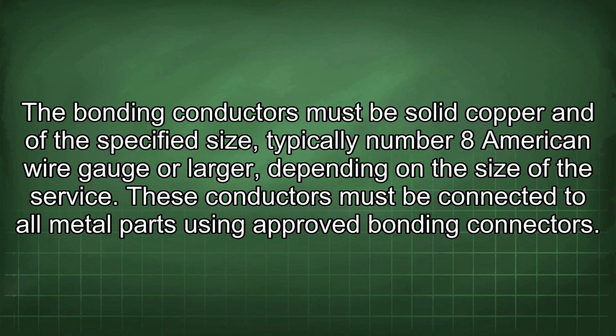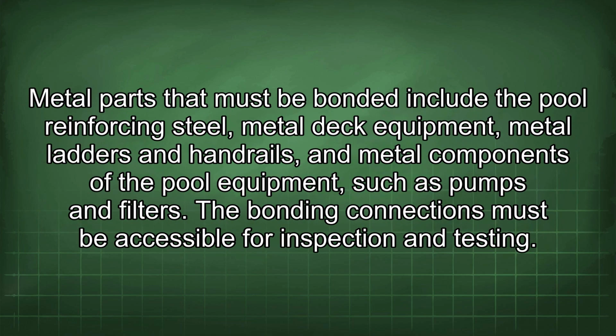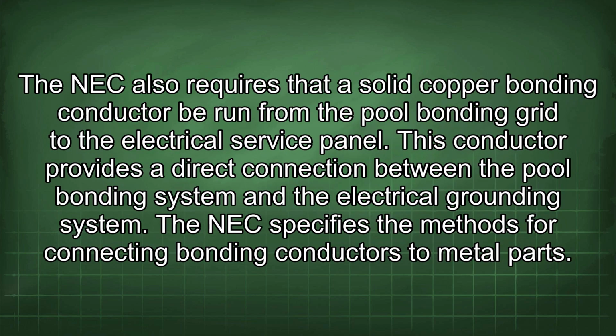These conductors must be connected to all metal parts using approved bonding connectors. Metal parts that must be bonded include the pool reinforcing steel, metal deck equipment, metal ladders and handrails, and metal components of the pool equipment such as pumps and filters. The bonding connections must be accessible for inspection and testing. The NEC also requires that a solid copper bonding conductor be run from the pool bonding grid to the electrical service panel. This conductor provides a direct connection between the pool bonding system and the electrical grounding system.